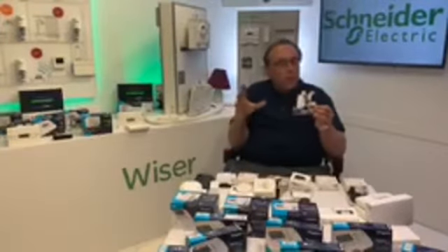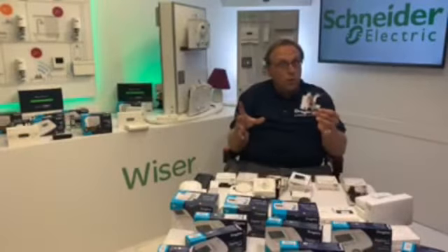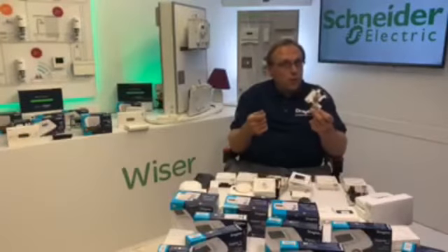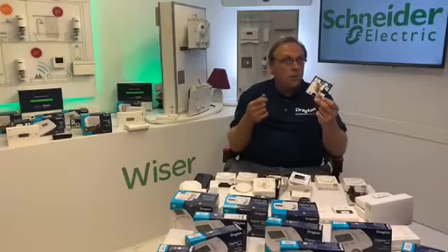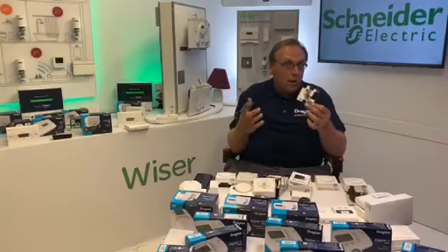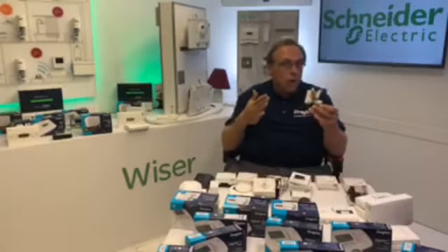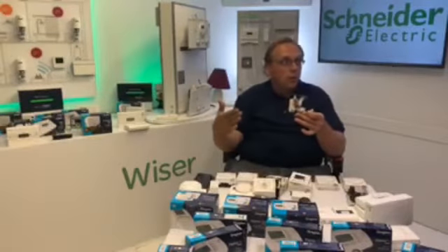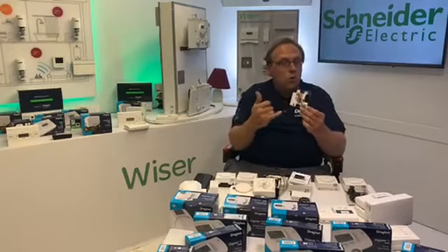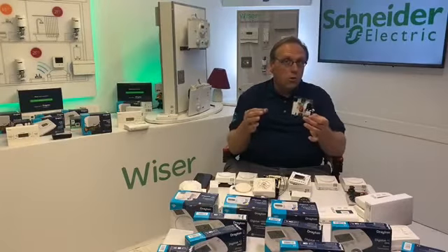What I will say is if you're using it as a 2-wire thermostat, you just need to be a bit mindful of the current that you're drawing, because it can handle anything up to 6 amps, but depending on where your current range falls depends on where you wire it. So you would either use terminals 2 or 3, depending on the current that you're drawing.